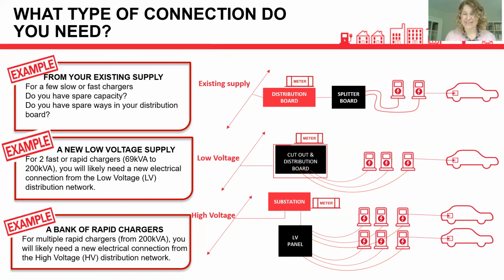If you're looking to install a fair few more chargers, say anything above 150 to 200 kVA, you're likely instead to be granted a point of connection at high voltage. This requires you to have a substation on your site, and that supply will then come into some kind of LV panel where it's split up and directed to where you need it.